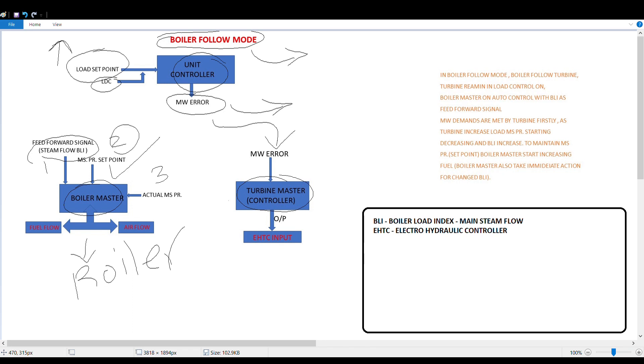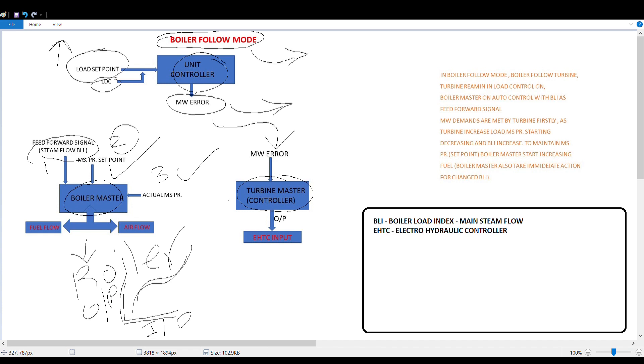The second input to the Boiler Master is the MS pressure set point — the pressure the controller wants to maintain — and the third is the actual MS pressure the unit is running at. On receiving these three inputs, the Boiler Master outputs fuel flow and air flow commands. The Boiler Master is fed with a curve supplied by the OEM; depending on the input values, the output values are decided. These can be adjusted as per the controller's choice and unit stability requirements.